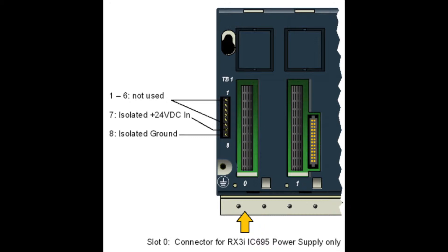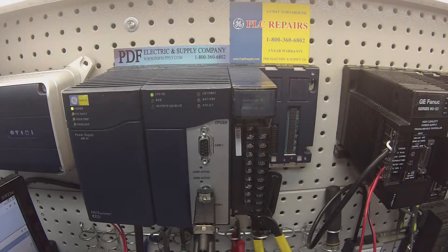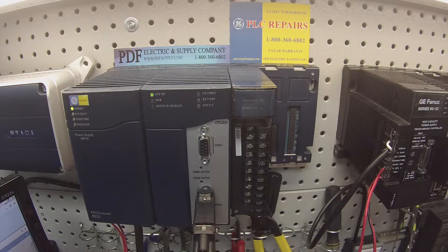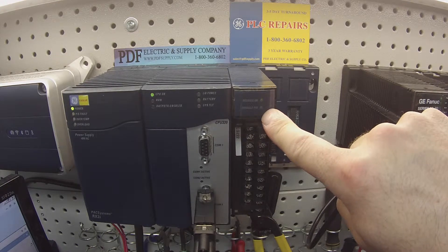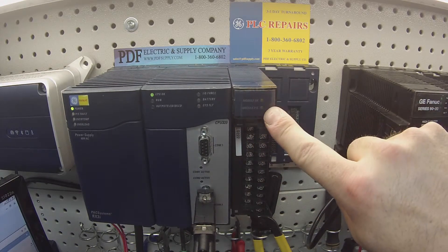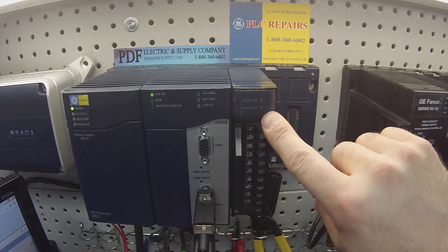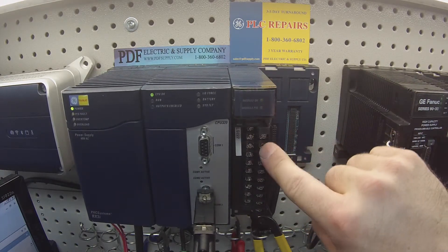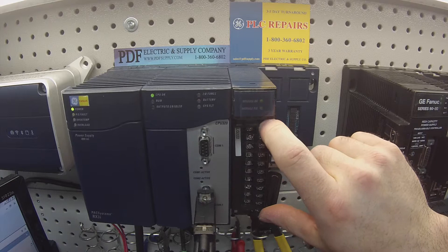On the far left side of the rack, you'll notice something labeled TB, and on the bottom two screws of that terminal strip are the inputs for your positive and negative leads from an external 24 volt power supply. My negative lead is in the bottom most screw and my positive lead is in the second to the last screw. Once you've got 24 volts going through there, you should have this light on. Make sure you have both lights on and that this is working properly, otherwise you won't be able to follow the test.